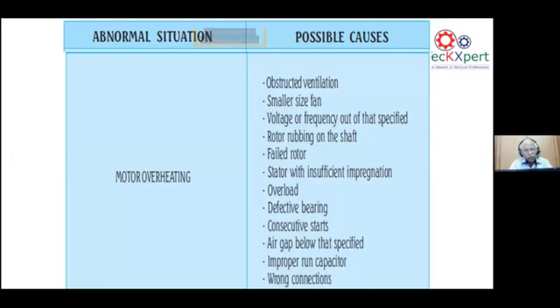Then the smaller size fan: many of the old OEMs or old motors had a smaller size fan. In fact, some 20 years back, we used an aluminum type of blade with a heavy fan, so that if you stand almost 3 feet, almost 1 meter, in front of the motor, you can feel the flow of the static pressure of the fan at the back of the motor. So the fan has to give you better ventilation or a better air throw across the motor fins to remove the heat from the motor, and the heat transfer should be excellent as such.